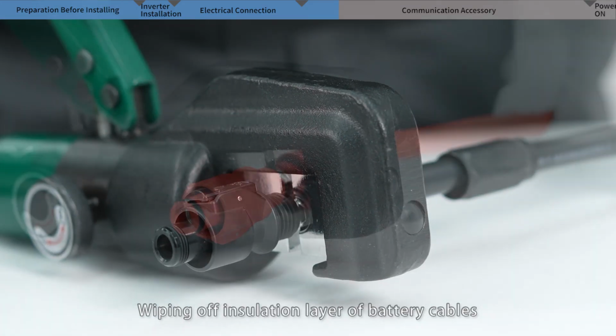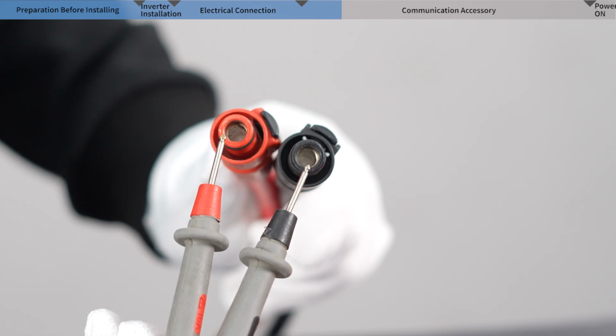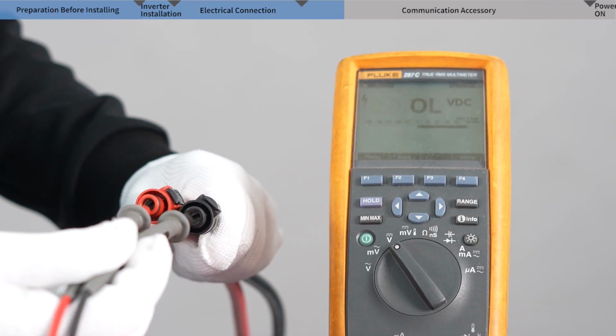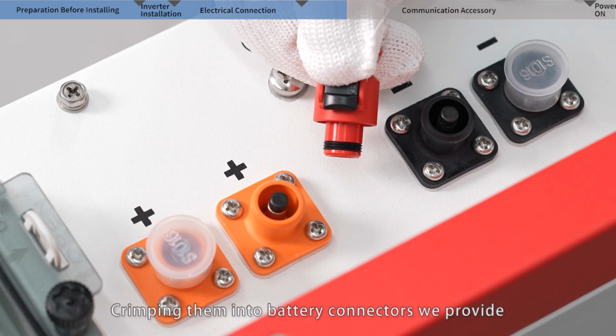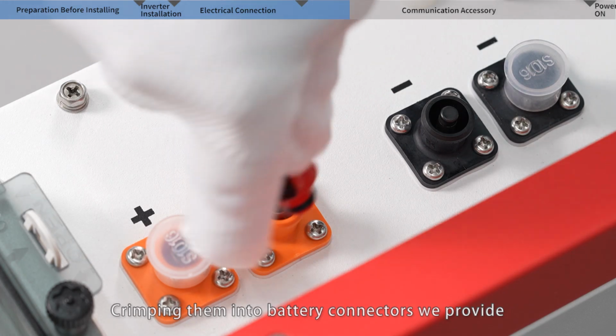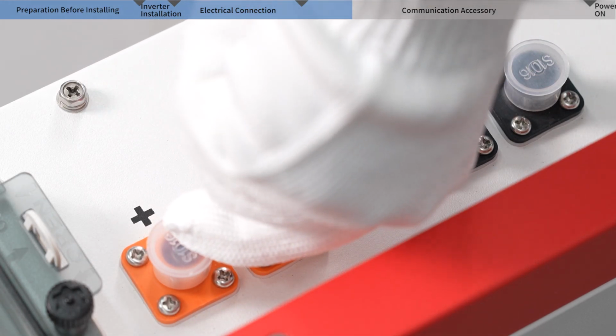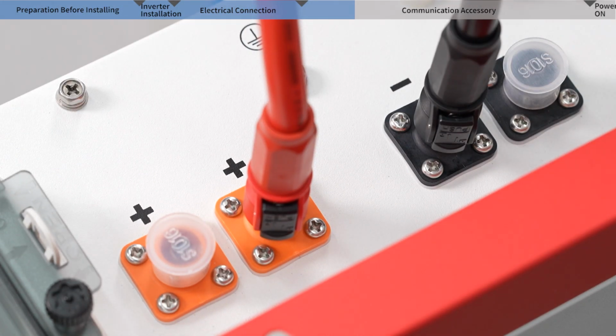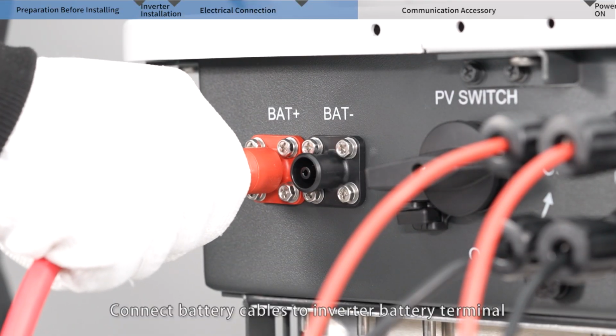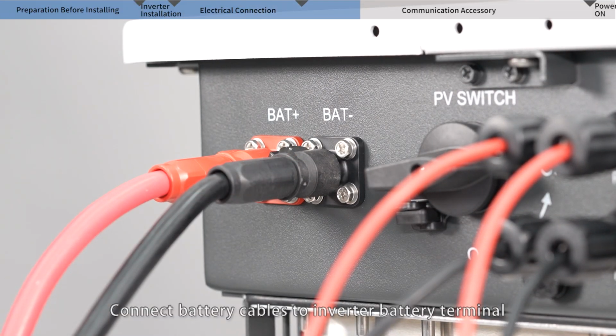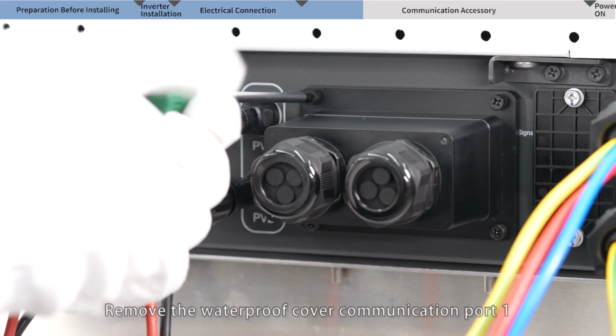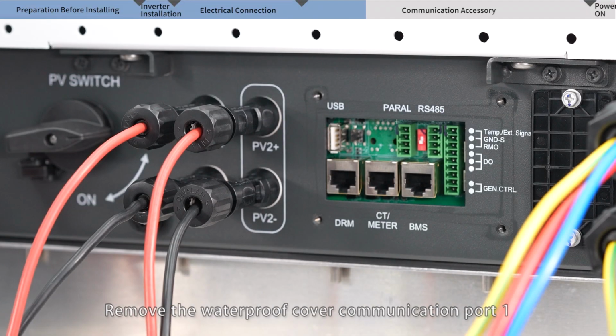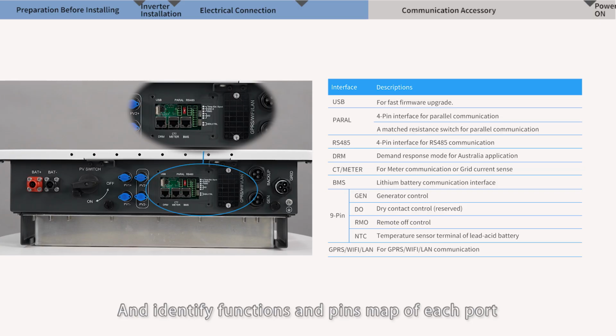Wipe off the insulation layer of the battery cables. Crimp them into the battery connectors we provide. Connect the battery cables to the inverter battery terminal. Remove the waterproof cover of communication port 1 and identify the functions and pin map of each port. Use as per actual demands. CT communication.